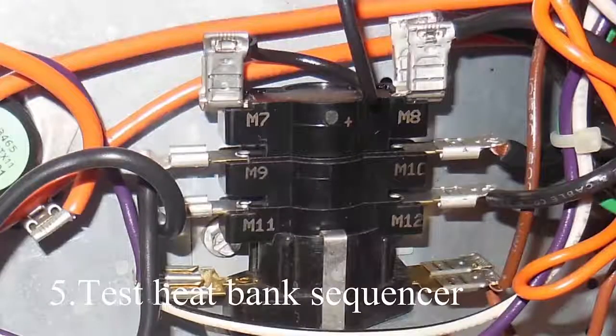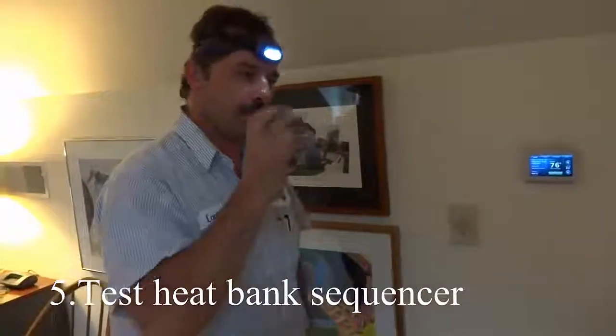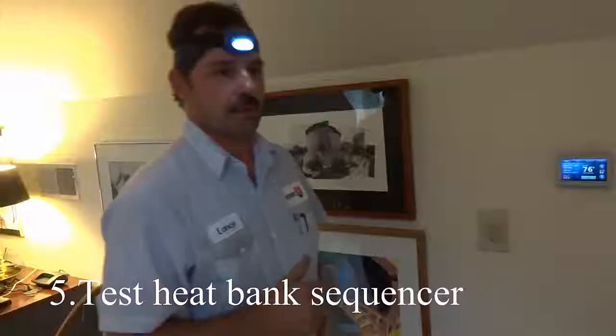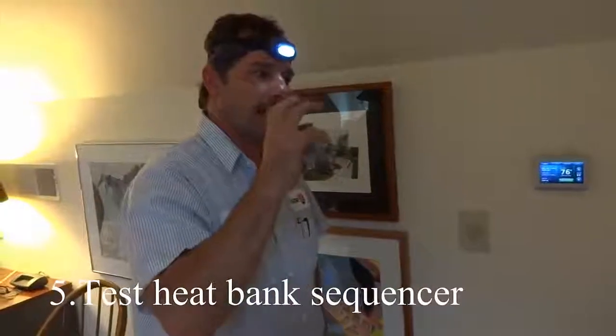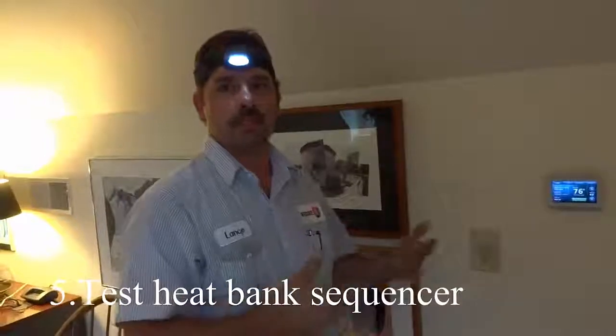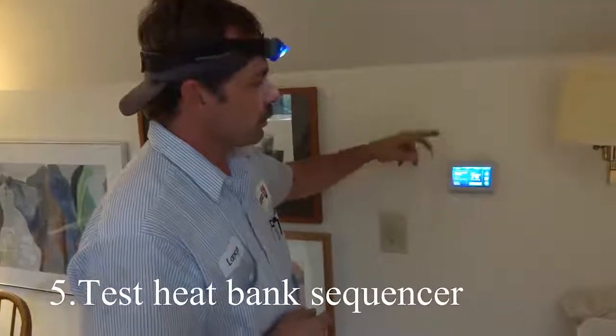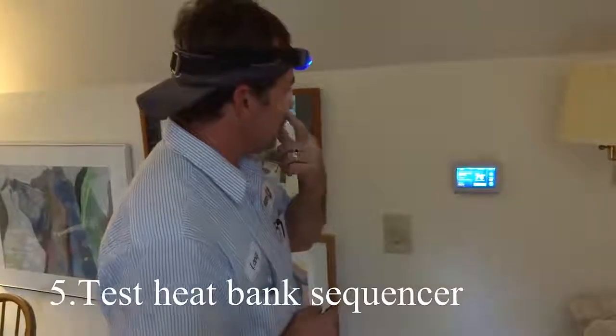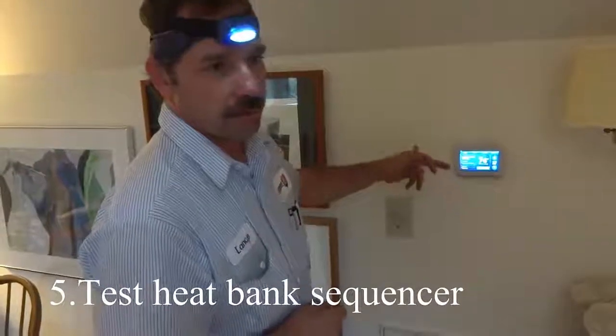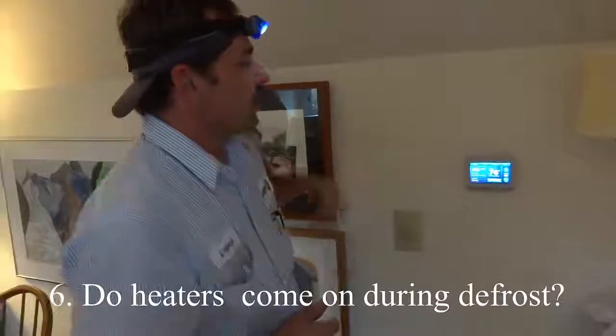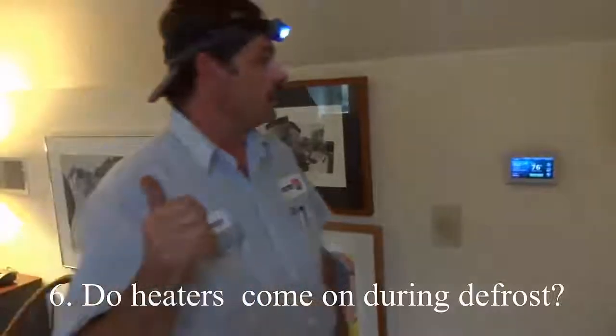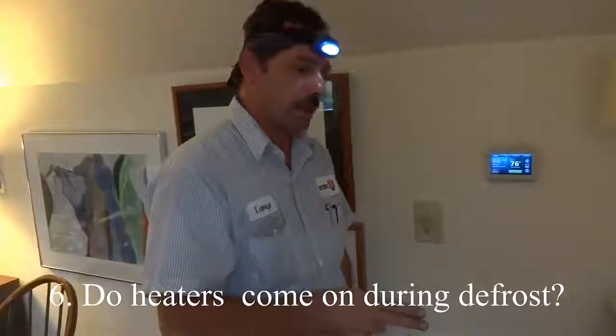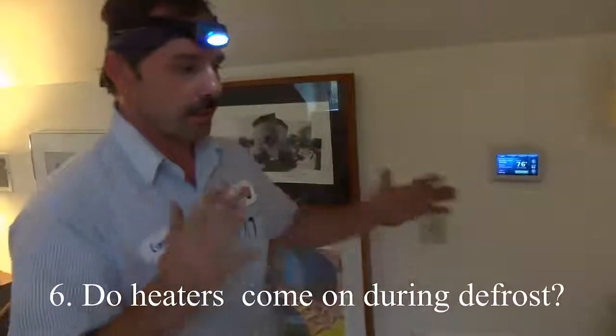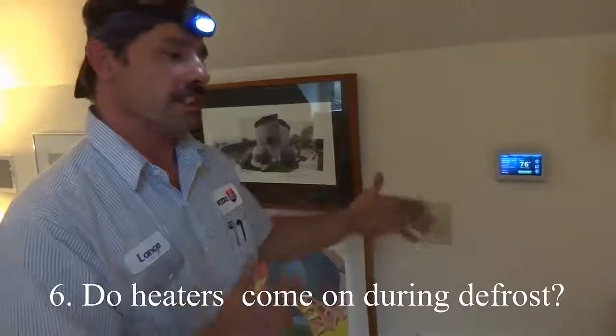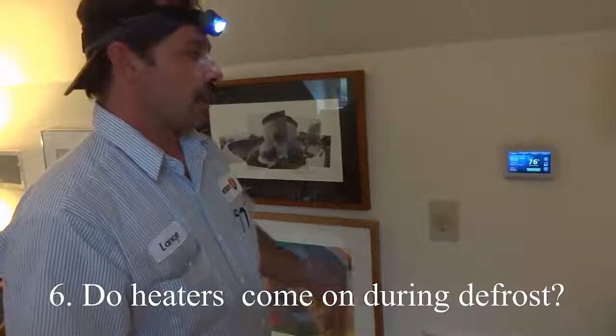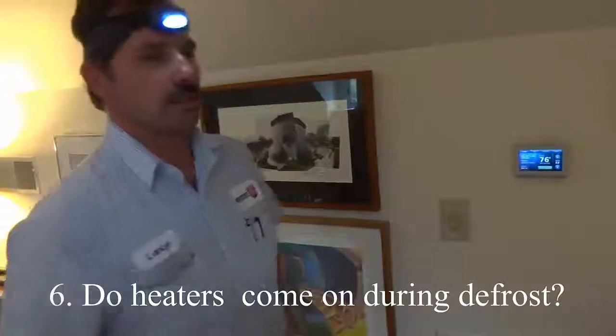Number 5, the heat bank sequencer is checked for proper operation. Maybe 30 seconds in between each stage, so you don't have a light dimming because it's pulling a considerable amount of amps. Generally, you'll have a 3-degree swing between first and second stage heat, and you may program in a 5-degree swing. When the first stage comes on and it's cold outside and it goes into defrost mode, it'll kick in the heaters, and you're actually turning back into an air conditioning mode in defrost until you melt the ice, and to compensate for that, it turns the second stage heaters on.